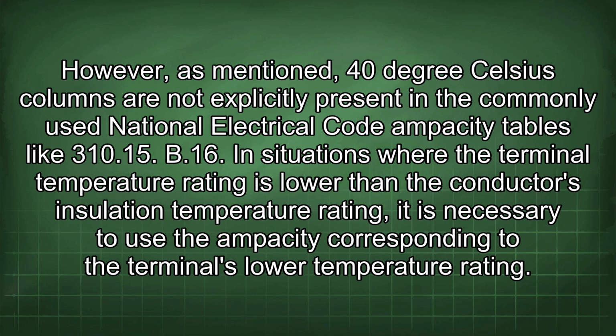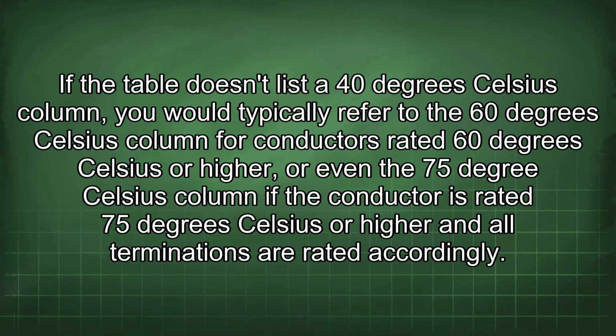In situations where the terminal temperature rating is lower than the conductor's insulation temperature rating, it is necessary to use the ampacity corresponding to the terminal's lower temperature rating. If the table doesn't list a 40 degrees Celsius column, you would typically refer to the 60 degrees Celsius column for conductors rated 60 degrees Celsius or higher, or even the 75 degrees Celsius column if the conductor is rated 75 degrees Celsius or higher and all terminations are rated accordingly.